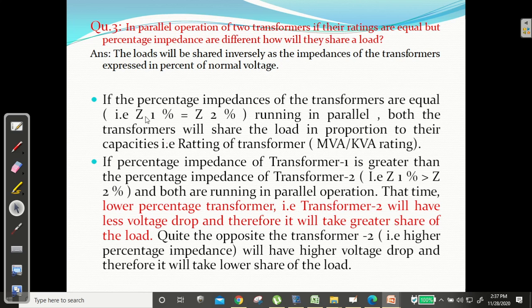But if percentage impedance is different, what will happen? Whichever has lower percentage impedance, voltage drop in the winding will be less and it will share more load. If it is more, it will share less because the drop is more. Okay, so that may happen. So lower percentage impedance transformer will have less voltage drop and therefore it may take a greater share of load. Okay, so percentage impedance should be same. That is a condition we have.